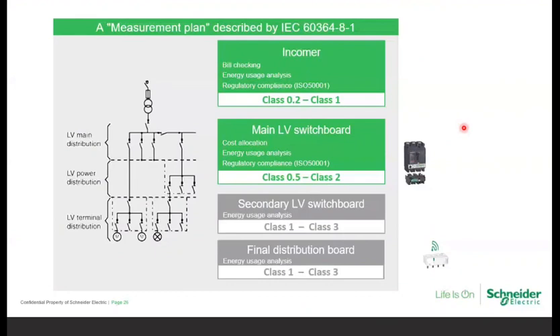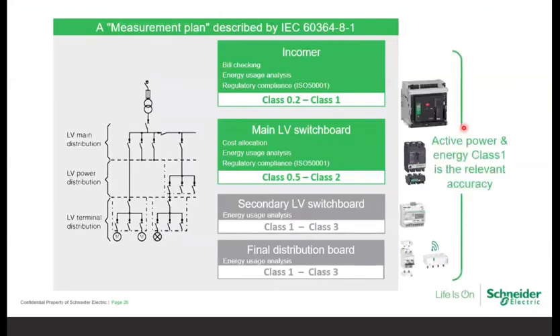Who is suggesting which level of installation, which class of accuracy is recommended? So this is talked about in IEC 60364-8. These standards will tell us at what level of installation, what level of accuracy is important. So it is just talking about the level of accuracy. How to achieve that accuracy? Either with the inbuilt metering of the protection devices or the external CTs and meters. That is our choice. But this standard talks about the accuracy at the level of installation.